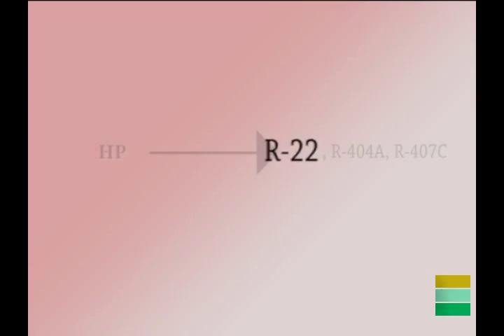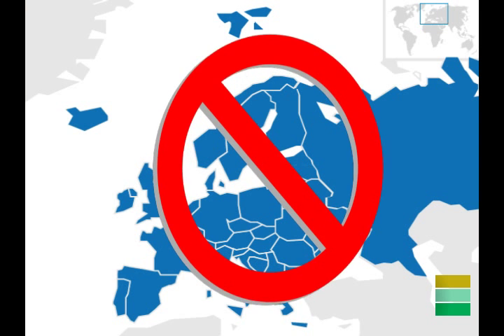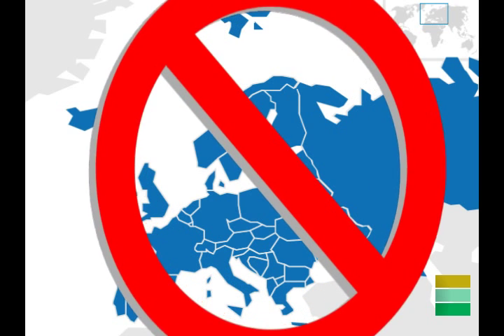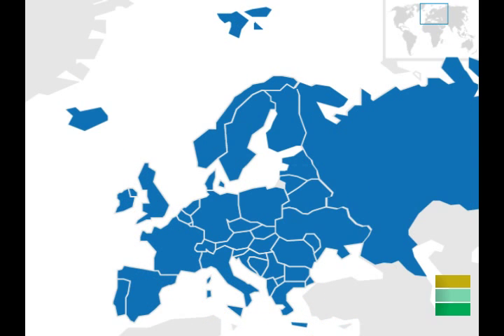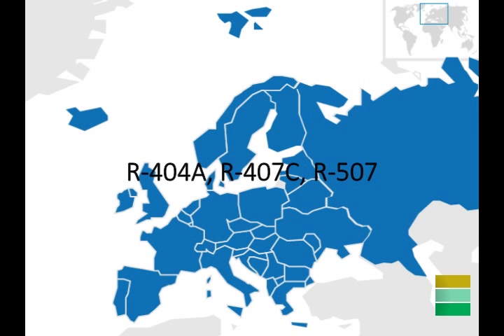Among the high pressure gases, R22 refrigerant contains chlorine, which is very effective at removing certain unwanted impurities. In any case, R22 is one of the cheapest refrigerants available, therefore the most suitable product for cleaning. In countries where it is not available or its use is prohibited by law, another refrigerant of the same pressure such as R404A, R407C, or R507 can be used.